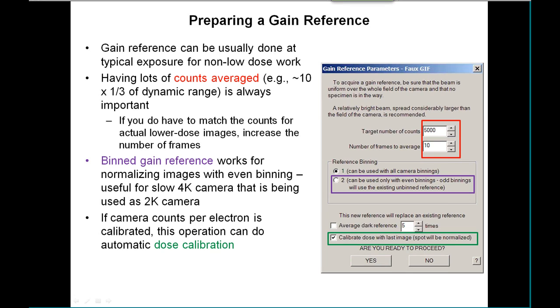If you find that because of non-linearities you have to take your GAIN reference at a lower level that matches your low-dose images, then you should increase the number of frames so that you come up with the same total number of counts. There is also the capability to take a binned GAIN reference instead of just the unbinned one, because some 4K cameras are very slow and more useful as 2K cameras. You can forget about the 4K aspect and take a binned GAIN reference as 2K, using even binnings that will be normalized from that.